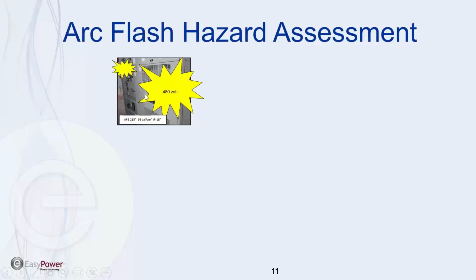Downstream, it's going to be a little less because it's protected by the main, but you have to protect people for the whole switchgear for the highest level. So 96 is what you need. And of course, we only have a 40-calorie arc flash suit, so it's not enough. Once they changed the transformer out, it went down to 28 calories, and they got a 1,500 kVA transformer instead of 5,000 kVA, and the impedance was much higher.